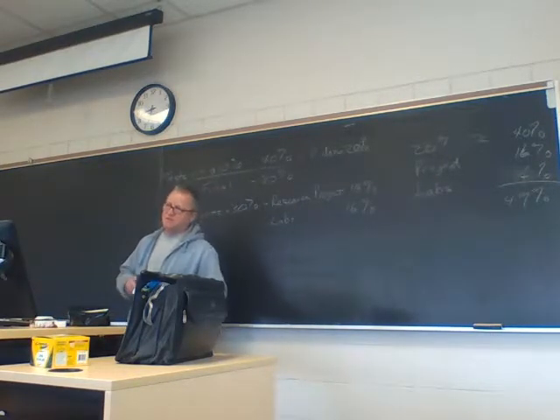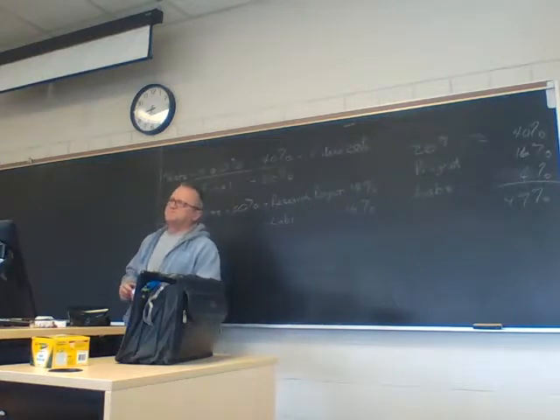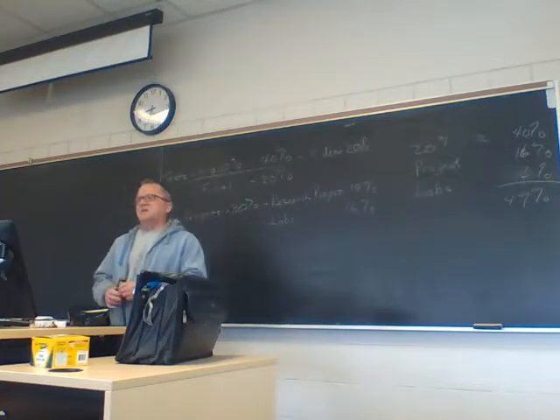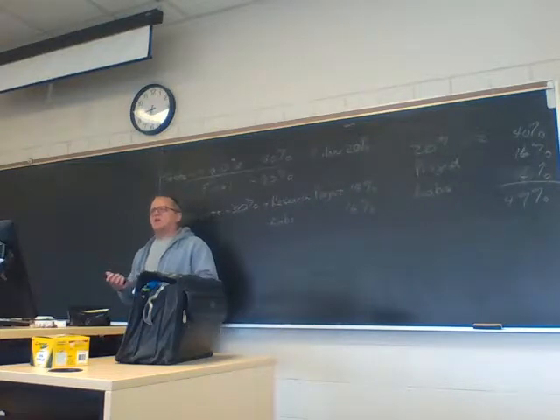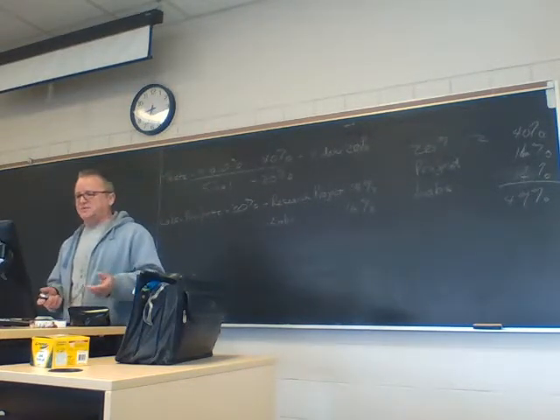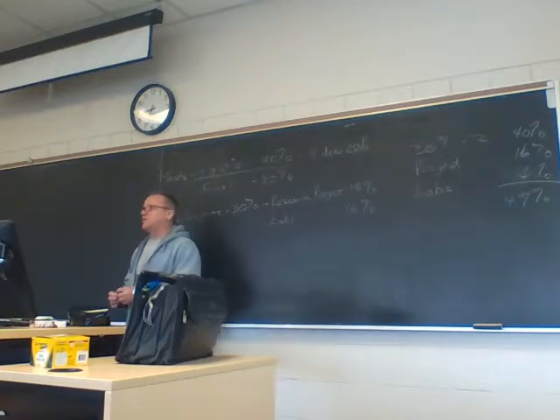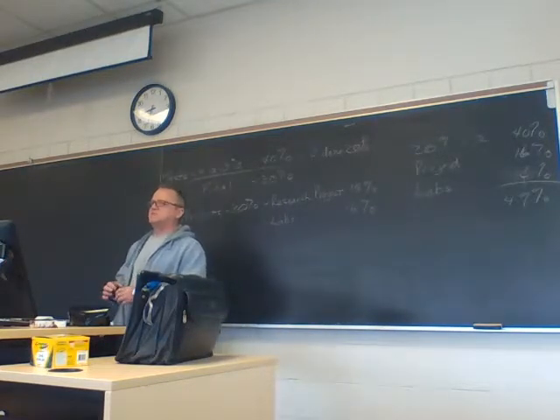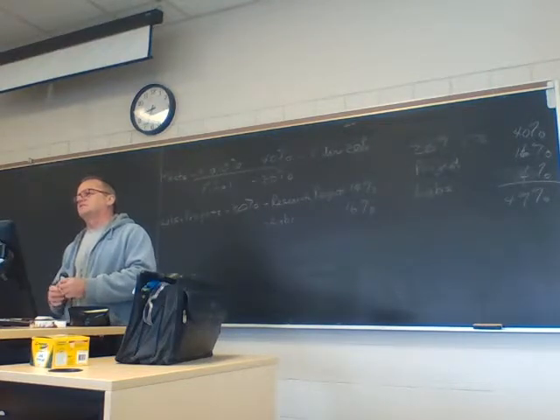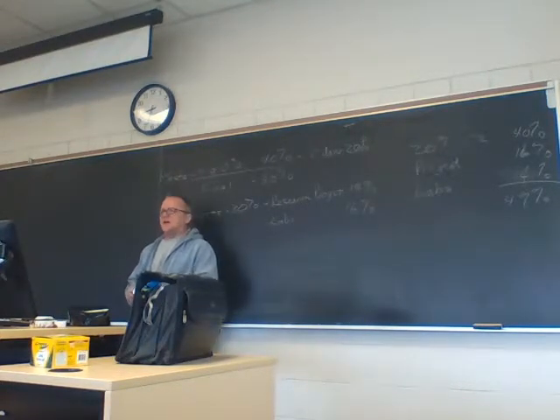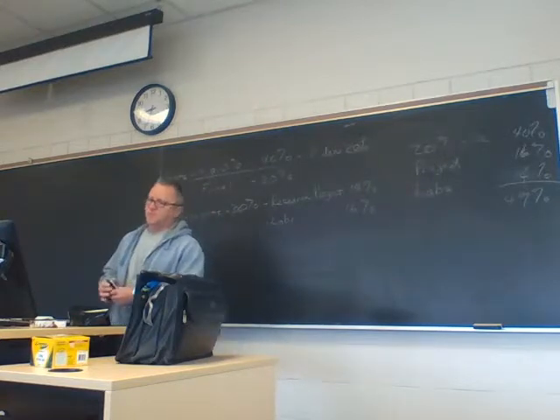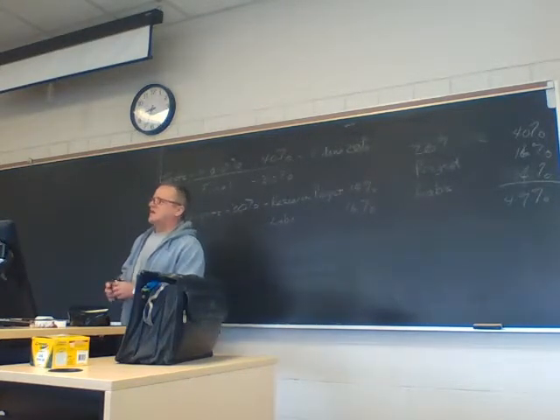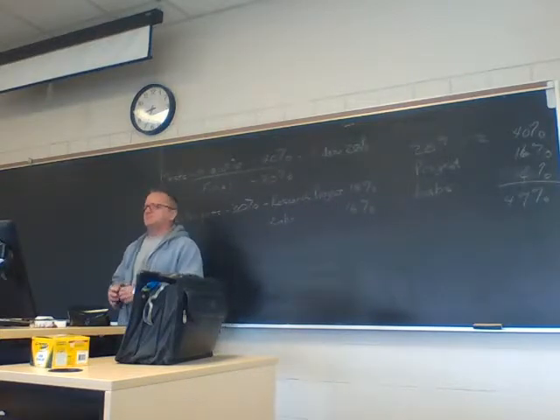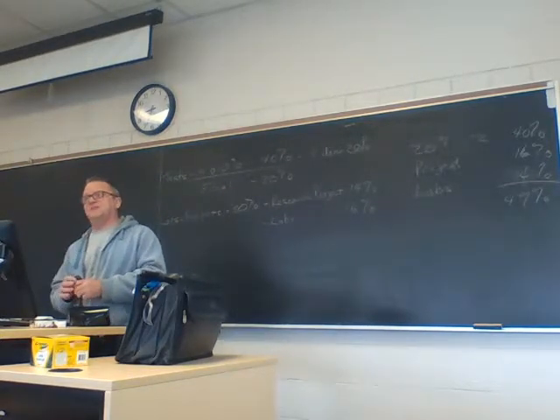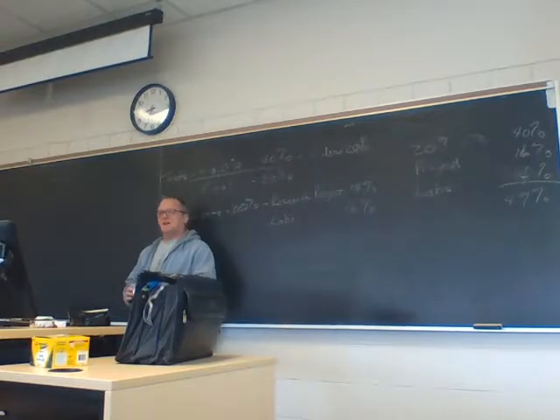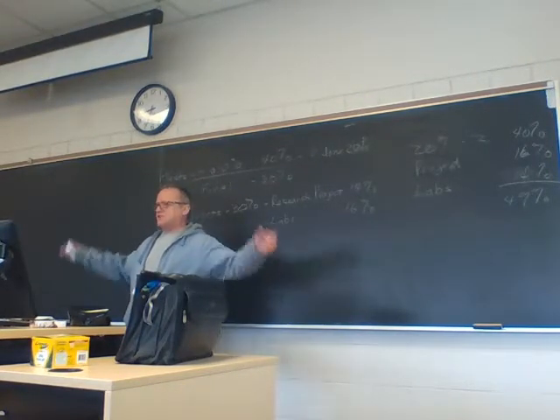I'm in a situation on a project where we talk about generators too, but they bought a used backup generator for the facility that we're going to install. And the system voltage is 600/347. And he bought this generator from a guy who told him, yep, it's 600 volt. And we got this pretty big generator in a trailer, and it's got all the ventilation and louvers and everything in it. And the nameplate says 208 volts.